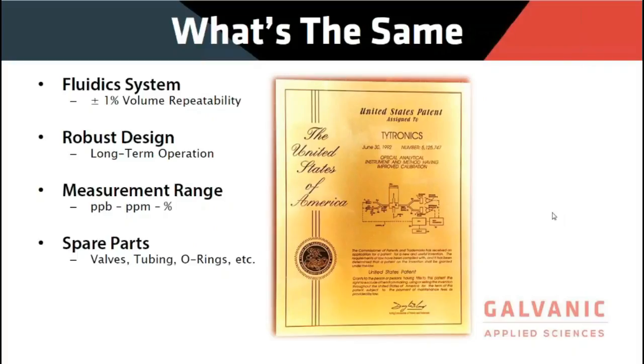But all of these systems are built to last and last. As long as you take care of them, they will work. For measurement range, we can go down to the parts per billion through ppm, grams per liter, and percent range. And most of the spare parts are universal for the Sentinel and AccuSeries. So the valves, the reaction cell, the tubing, O-rings, etc. If you have any stock of the Sentinel spare parts, you can still use them in the AccuSeries.